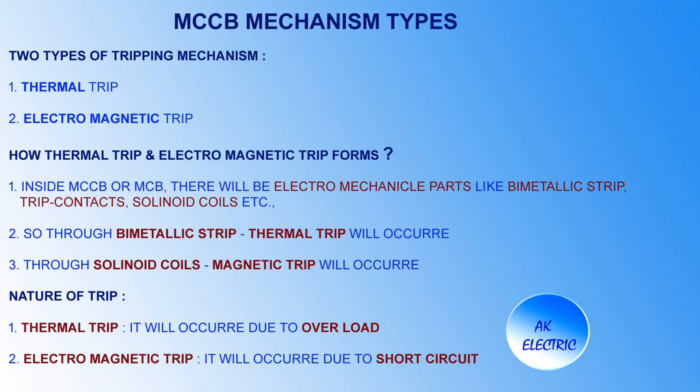MCCB mechanism types: there are two types of tripping mechanism — one is thermal trip and another one is electromagnetic trip. Inside MCCB or MCB there are electromechanical parts like bimetallic strip, trip contacts, and solenoid coils. Through bimetallic strip, thermal trip will occur, and through solenoid coils, magnetic trip will occur.